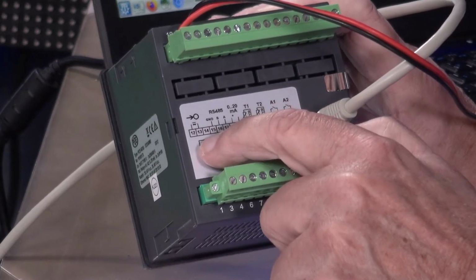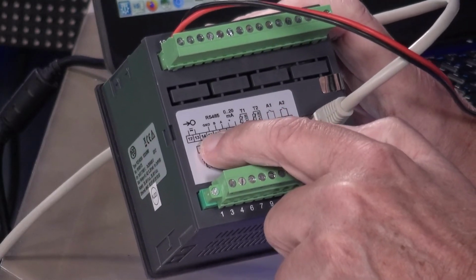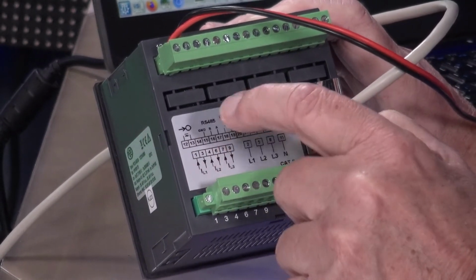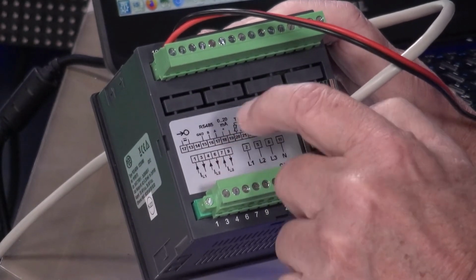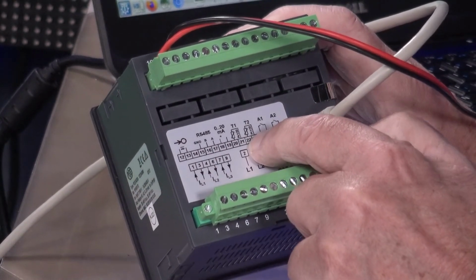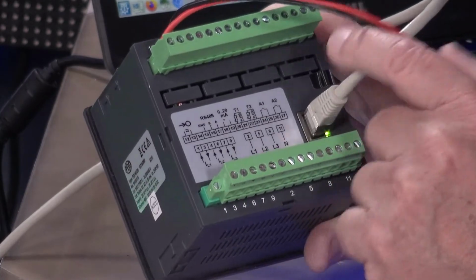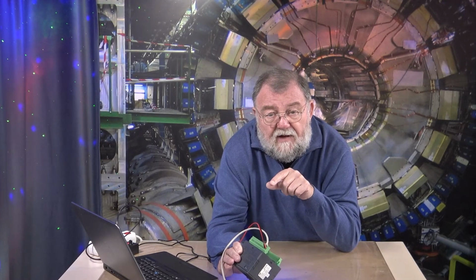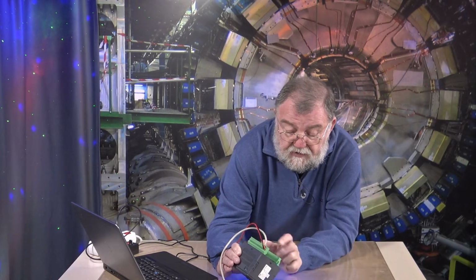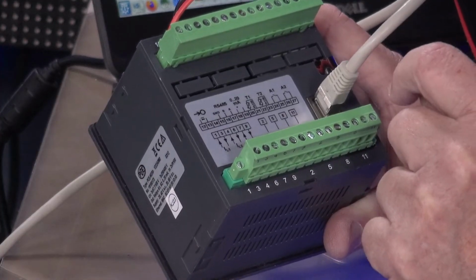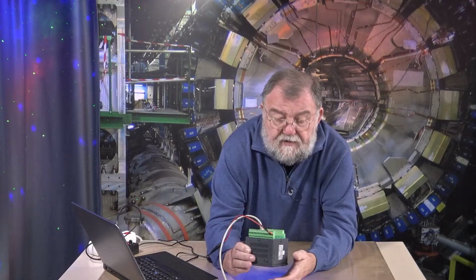So you can directly see where L1 goes in and out, L2, L3. And up here I have the connections for the RS485 power interface. I can connect two thermal elements and monitor temperatures. I can link them logically too, to set off an alarm whenever a temperature is over or under a certain step.